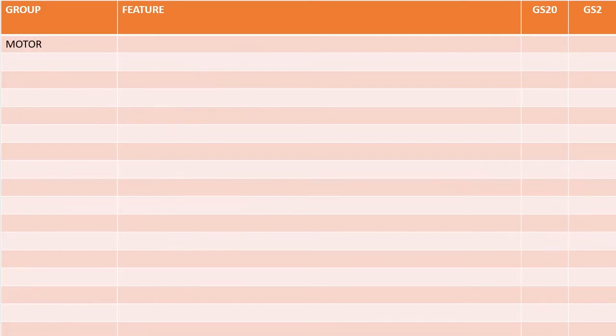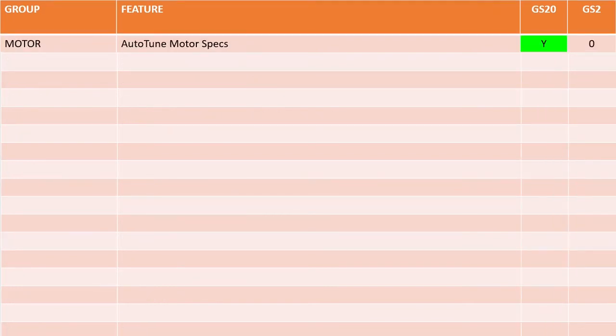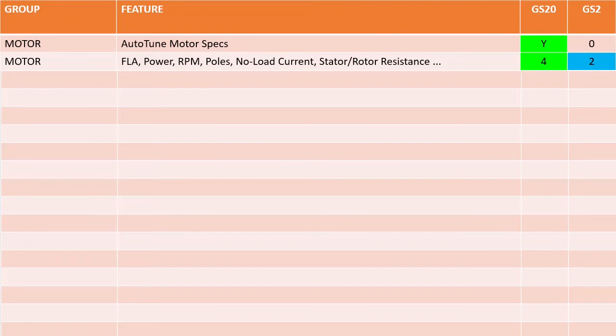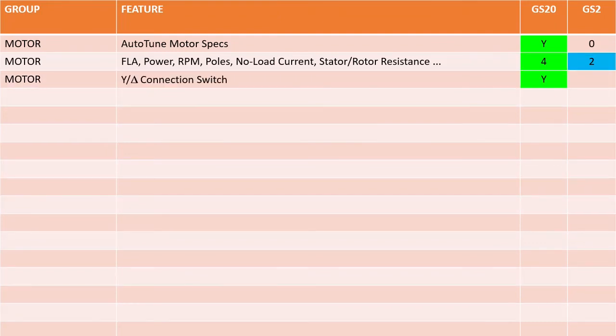The motor group gives us motor parameter auto-tuning and has the usual motor ratings, except the GS20 handles 4 motors and the GS2 handles 2. The GS20 can automatically switch between Y and delta connections to the motor in real time, so you can start out using a Y connection to get extra torque at low speeds and then, once it reaches the frequency you specify, switch to the delta configuration to get low torque but high speed. That does require a motor specifically designed for Y-delta switching.